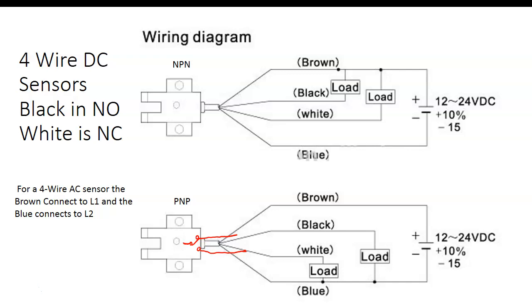I'm getting confused—I thought sourcing was connected to the positive. The sensor provides it: if your sensor provides a plus, then your loads have to be connected to a minus. So if your sensor supplies a plus, then it's sourcing. Gotcha. And over here, your sensor's loads are using a negative common—positive common, so your sensor's got to be providing a negative. So this would be a sinking sensor.